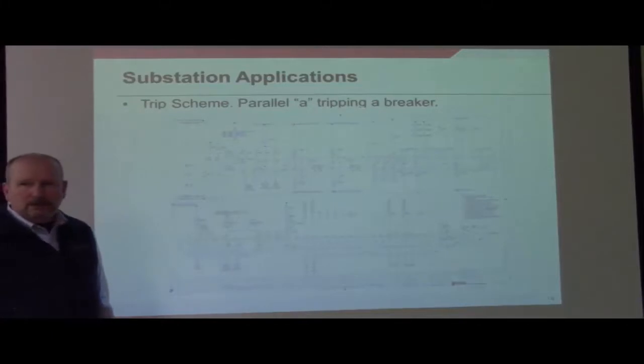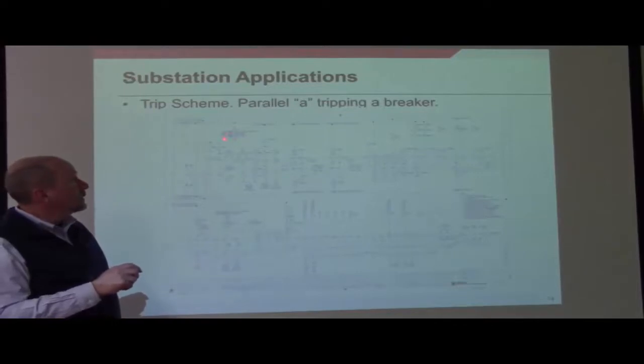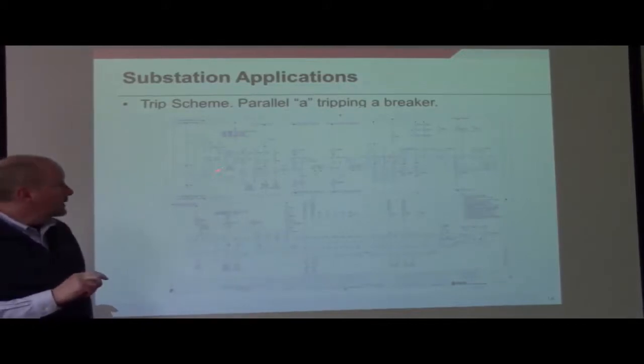If we go over to a particular trip scheme, right over here in the drawing is the circuit breaker, and we're going to cover this in great detail in the next class. And right up here are all of the different things that will trip that circuit breaker. In this case, they're not drawn out, they're just listed with references to the drawings that they actually show up on. But in a wiring system, those are all wired in parallel, so any one contact can close and trip that circuit breaker. And that's how trip schemes work.